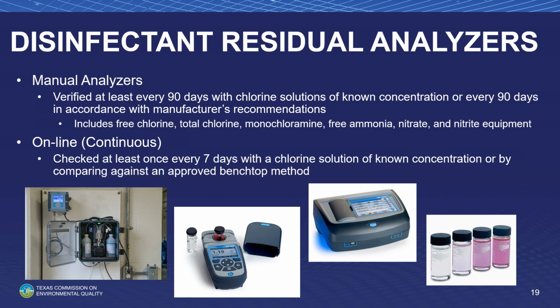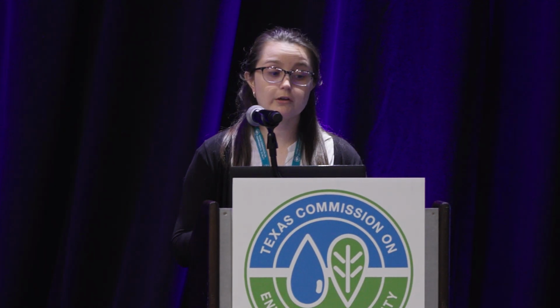Online continuous disinfectant residual analyzers need to be checked at least once every 7 days with a chlorine solution of a known concentration or compared against a benchtop method. For the chlorine analyzers, the online ones, once it doesn't read within range, or it doesn't compare against your benchtop or against the concentration, that's when you'll need to do a full recalibration of the continuous reader.